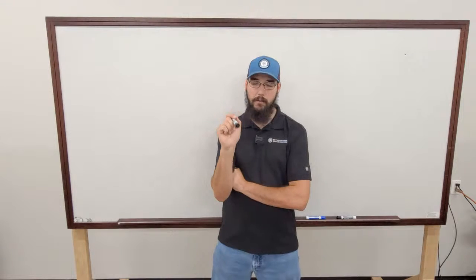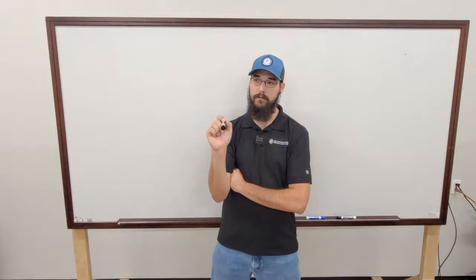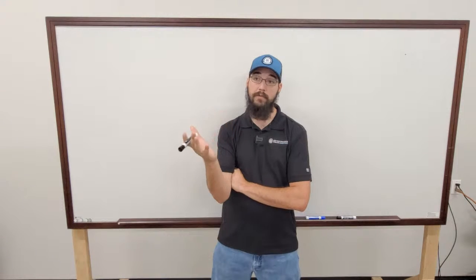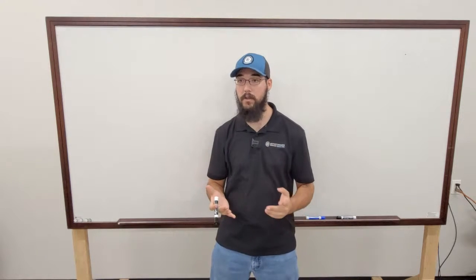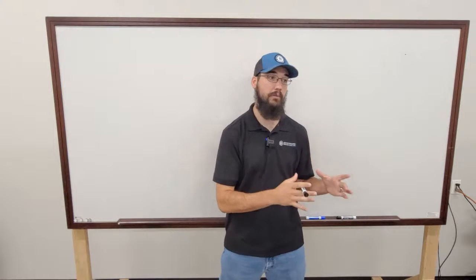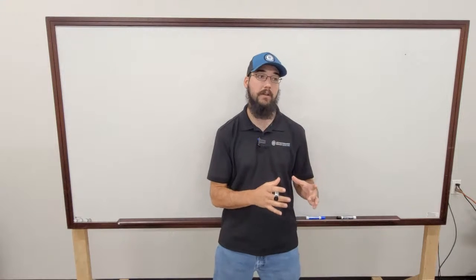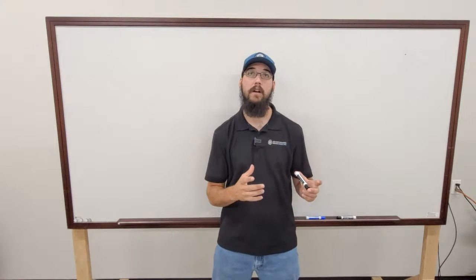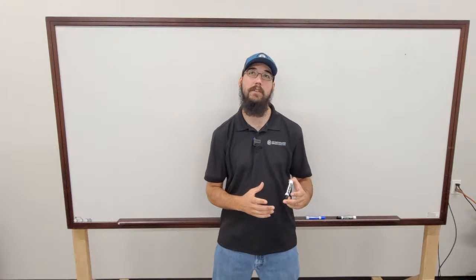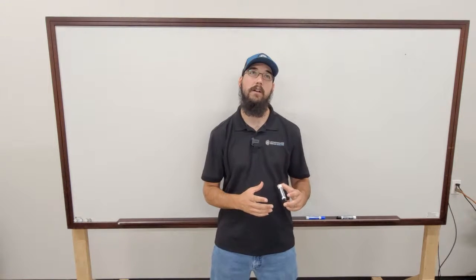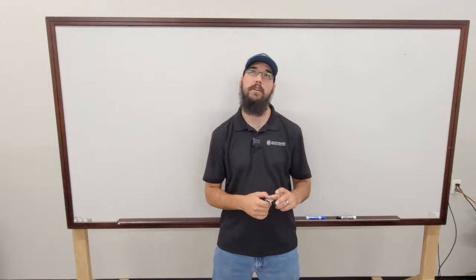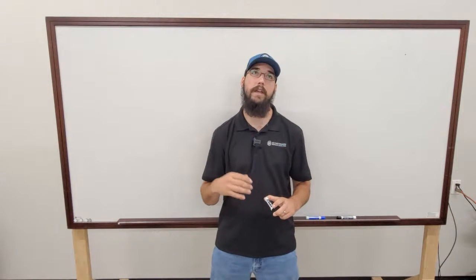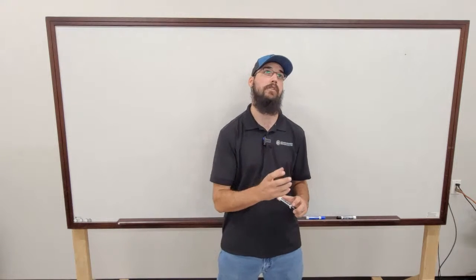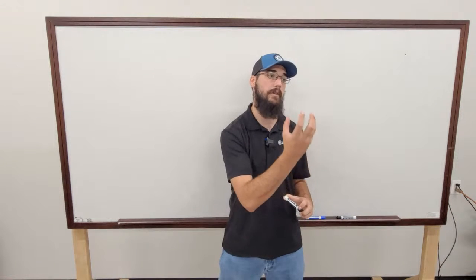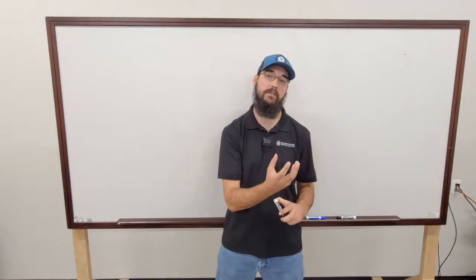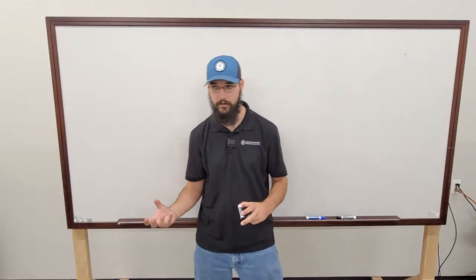Every machine is always going to start up fully unloaded. Or if it's, say, a screw or a recip, you're going to start with just one compressor. And typically, if that compressor has unloading capabilities, well, no, it shouldn't go straight to unloading at startup. When it's bringing that circuit in, it should allow that compressor to come in and stabilize, and it's not going to start unloading that compressor until later.